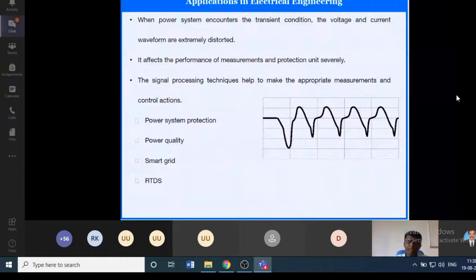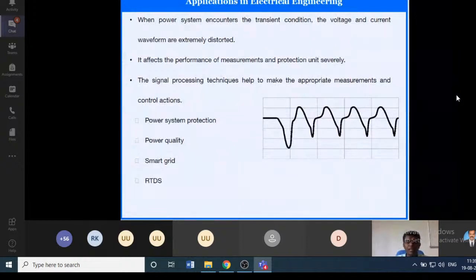So when we have a fault current like this, the relay has to detect and act effectively. This is the biggest challenge for the protection systems. When you have a distorted waveform, that will highly affect the measurement as well as the protection systems. So here we have the role of signal processing techniques. The signal processing technique will eliminate all the higher order terms and the disturbances other than the fault, and will detect only the fault related waveform, that is, the fundamental components and estimates. That helps to make the perfect decision and isolate the faulty section, right?